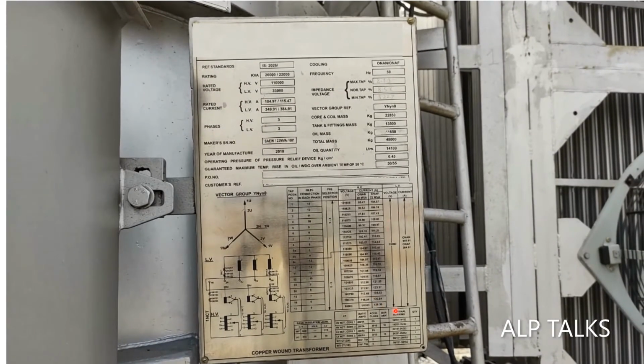Moving to another slide, this is the transformer specification. Power transformer 20 MVA by 22 MVA, 110 by 33 kV. This is the current rating. We have 22 MVA rated. So this is the structure. We have 50 Hz frequency. YN is the transformer rating. We have the transformer core coil weight, tank fittings, and oil mass. The total mass is around 48 ton. Oil is around 14 kiloliters. Generally PRV pressure 0.45 is mentioned here. 50-55 rise over ambient of 50, that's common. So the vector group we can see here.